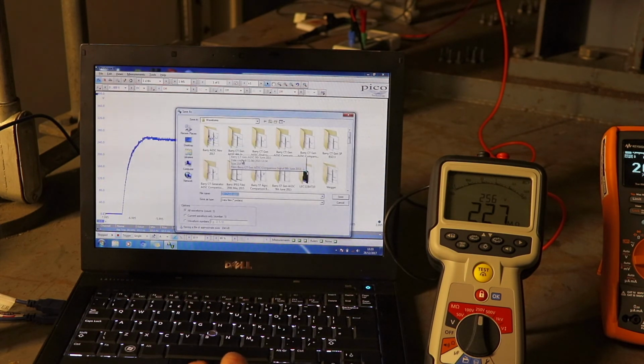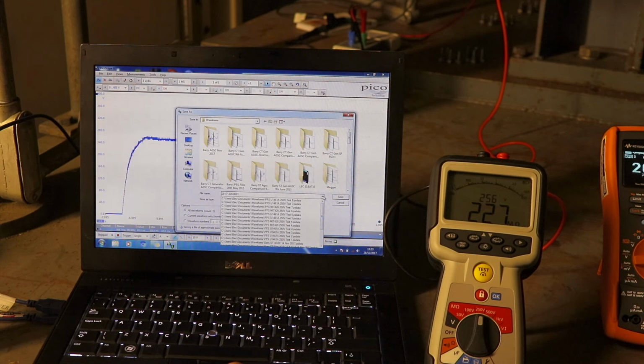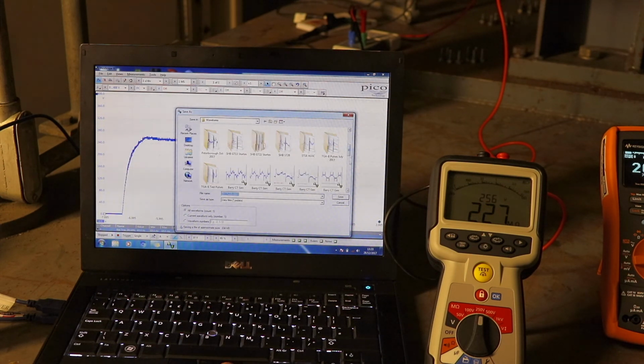Again, I've put a 1 gigohm resistor. Effectively, using the HV probe gives a 1 gigohm resistance across the output of the Megger, as well as in parallel with the rotor winding, so that could well be having an effect to an extent on the reading as well.